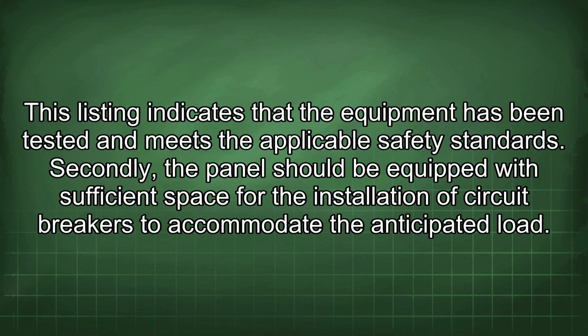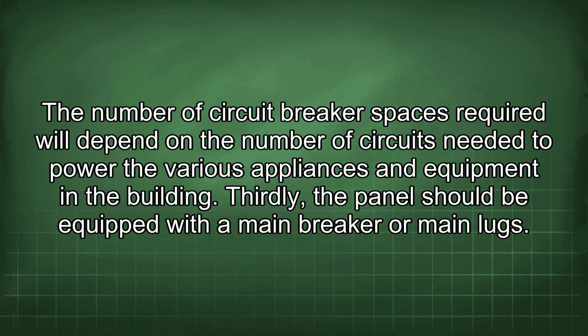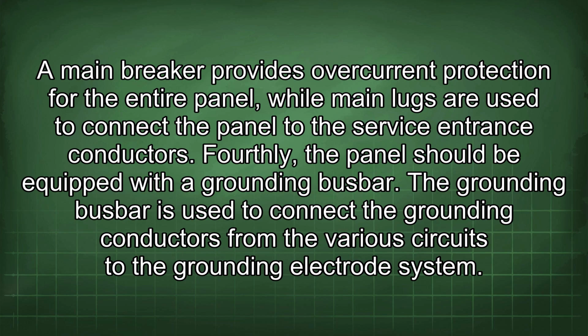Secondly, the panel should be equipped with sufficient space for the installation of circuit breakers to accommodate the anticipated load. The number of circuit breaker spaces required will depend on the number of circuits needed to power the various appliances and equipment in a building. Thirdly, the panel should be equipped with a main breaker or main lugs. A main breaker provides overcurrent protection for the entire panel, while main lugs are used to connect the panel to the service entrance conductors. Fourthly, the panel should be equipped with a grounding busbar. The grounding busbar is used to connect the grounding conductors from the various circuits to the grounding electrode system.